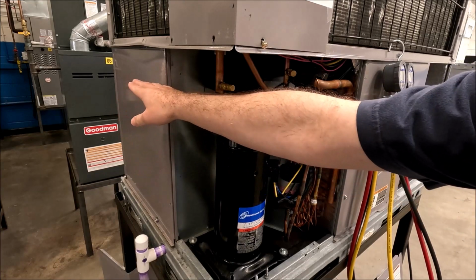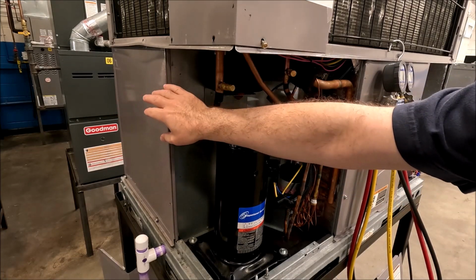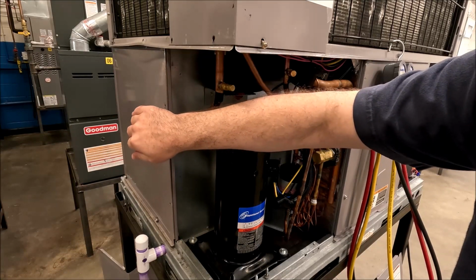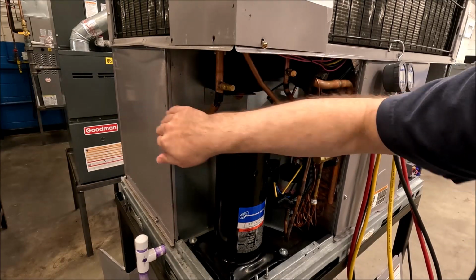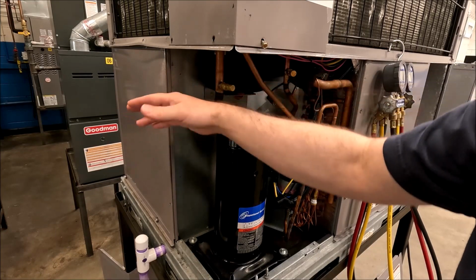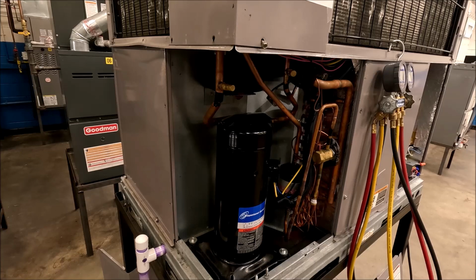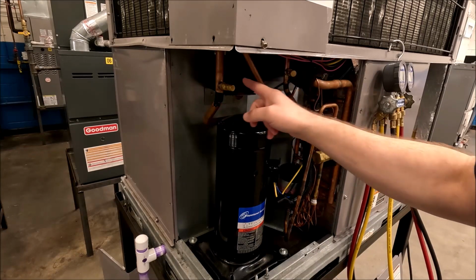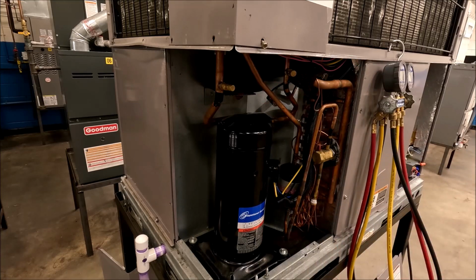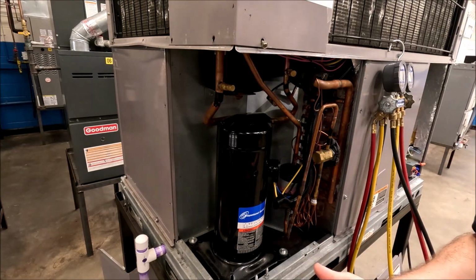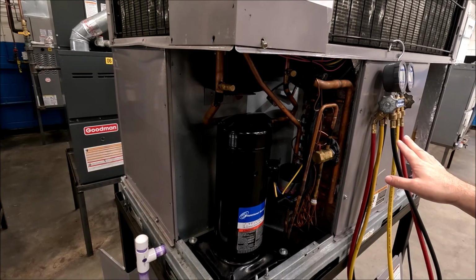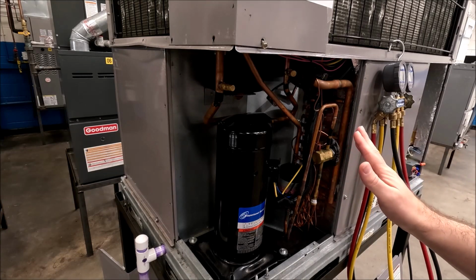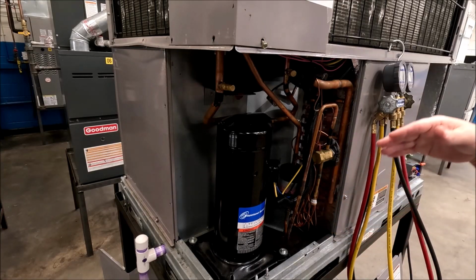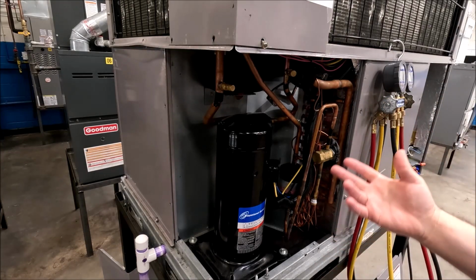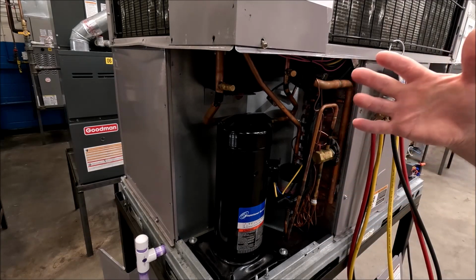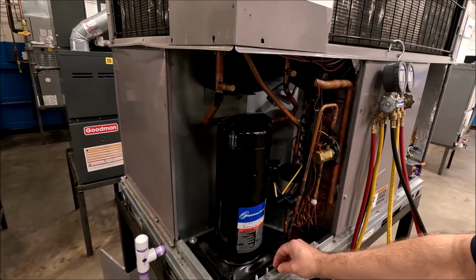And then of course, if we went any further that way, that would be where the return duct would be. You would have your crawl space area over there with the ducts going through and underneath the lintel and the foundation. You got your shroud over the ductwork to keep the water out. So we're going to look right here, and specifically we're going to take some gauges and hook up and talk about why we're doing that and what numbers we're going to get. So I started the unit just a second ago, so it'll take a few minutes to warm up. We're not going for picture perfect because we're inside. It's a beautiful day, of course. Inside it's like 72 degrees in here, so the numbers won't be exactly what you would expect out in the field, but you'll get the point.